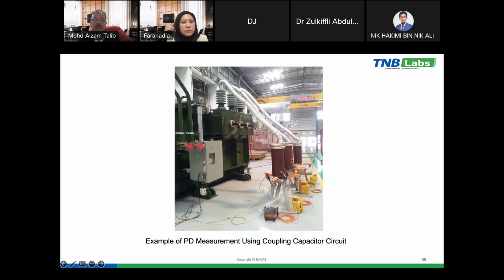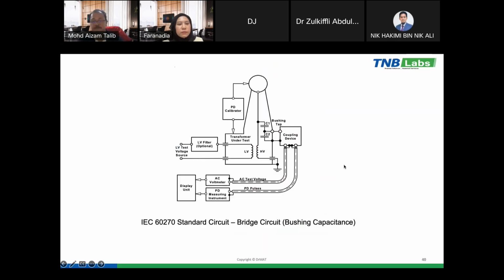And this is an example of the PD measurement using the coupling capacitor in the factory. Okay, here is the transformer. We inject the voltage through the LV and measure the PD at the HV. So we connect the coupling capacitor to the test object, and then here we have the matching impedance, the quadrupole, and each quadrupole will be connected through this fiber optic, and then goes to the measuring instrument, and this is the coupling capacitor or divider.